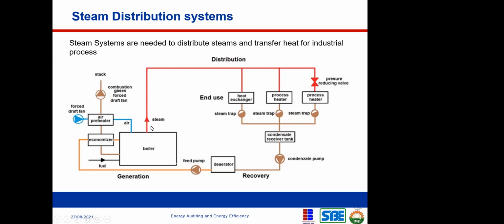Okay, so now this is steam. It flows through this red line and comes down here to the end use, where you have a heat exchanger, right? Now, after this heat has been used, it loses part of its heat. It now condenses back to water. So you now see here, we have a steam trap. The steam trap enables the water to escape from the system.